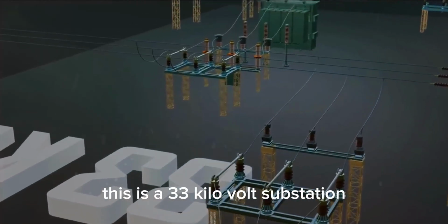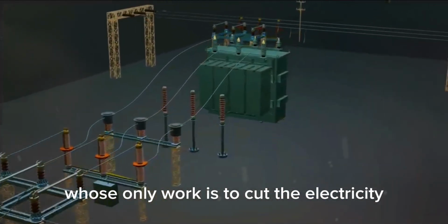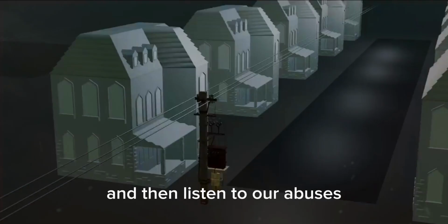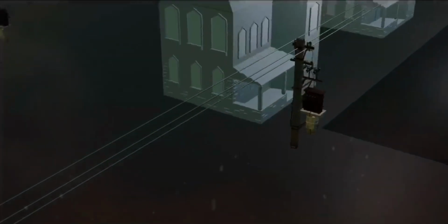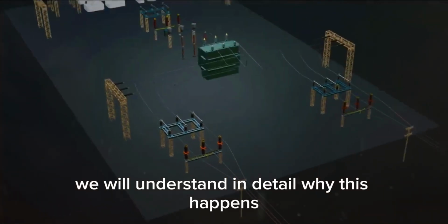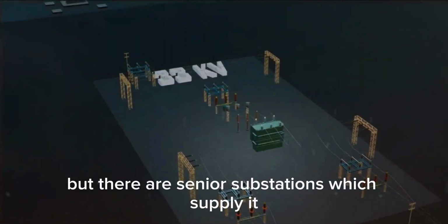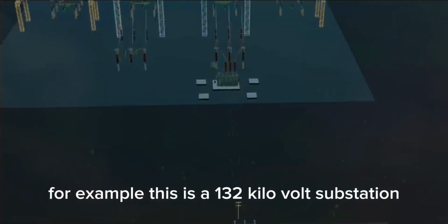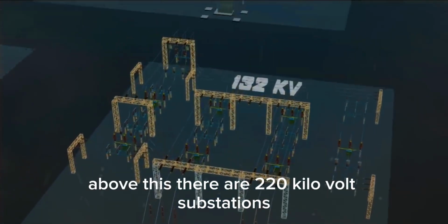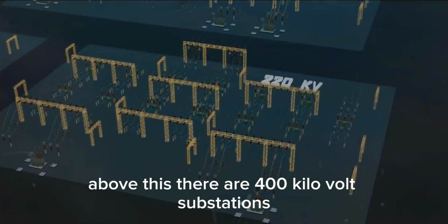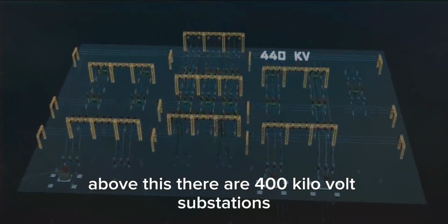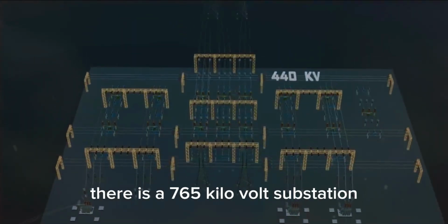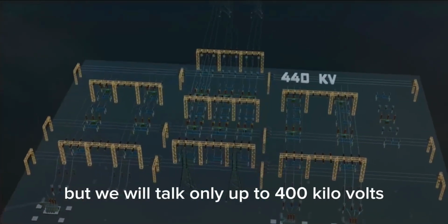This is a 33 kilovolts substation whose only work is to cut the electricity when we are sleeping comfortably and then listen to our abuses. We will understand in detail why this happens, but there are senior substations which supply it. For example, this is a 132 kilovolts substation. Above this there are 220 kilovolts substations. Above this there are 400 kilovolts substations. Now above these also there is a 765 kilovolts substation, but we will talk only up to 400 kilovolts. You will understand its reason later.